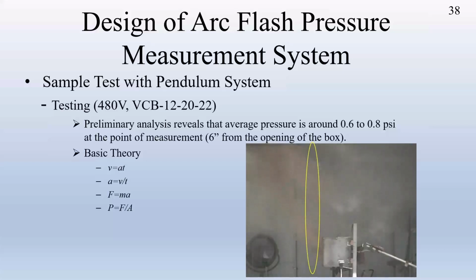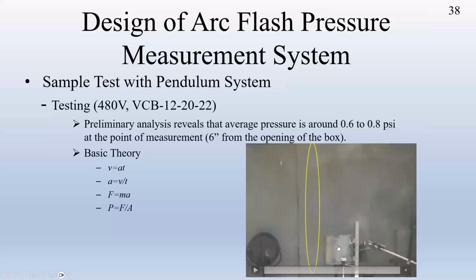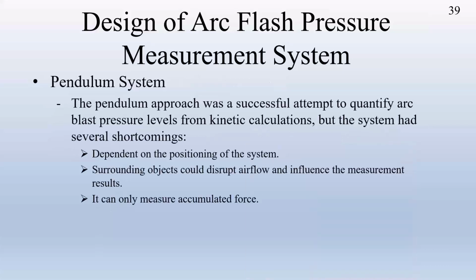And the other one that we have used is, during the arc flash, I have a high-speed video over there. So based on two consecutive frames, I will be able to look at what is the airflow speed, and then from the airflow speed, I will be able to estimate the pressure. But for this one, you need the open field so it doesn't obstruct the airflow. And arc flash testing is relatively expensive. Normally you are talking about $1,500 to $2,000 per test. So we basically say, okay, well, yes, it works, but it's not really an economic solution. We have a limited budget.